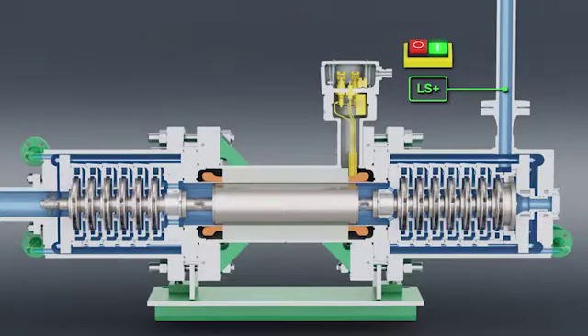The liquid is pushed through the impeller into the motor and passes through rotor and drilled shaft to the second side and the pressure is even more increased. This flow is also cooling the motor and removes the heat.